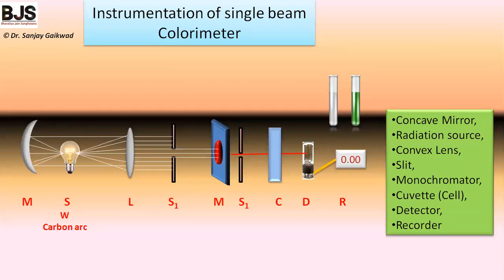Looking at the instrumentation of the colorimeter, it contains a light source, mirror, lens, slit one, monochromator, slit two, the cuvette, detector, and recorder. Polychromatic light is made parallel by the lens and then passes through the filter or monochromator, which selects a single wavelength. The light then falls on the cuvette where it is partially absorbed, and the remaining transmitted light falls on the detector, which gives a response measured by the recorder.